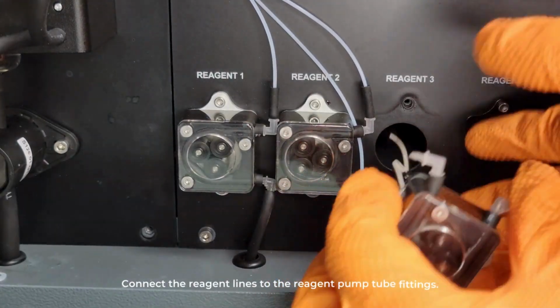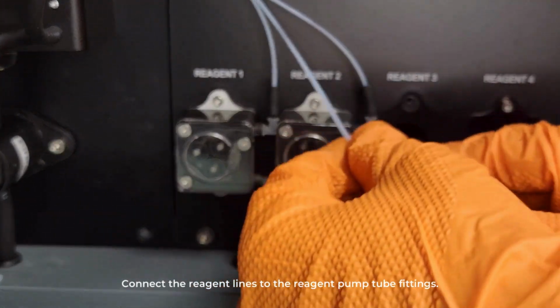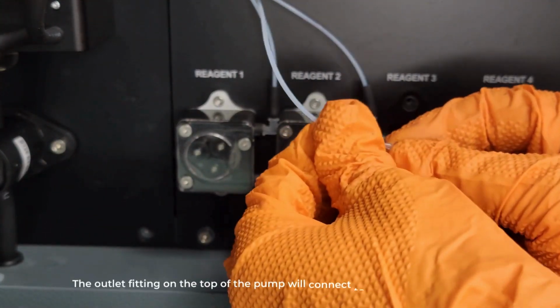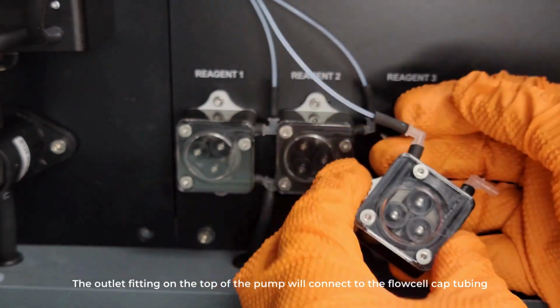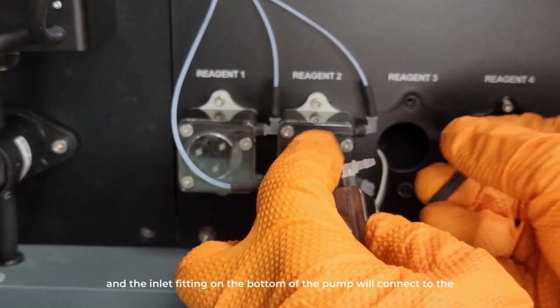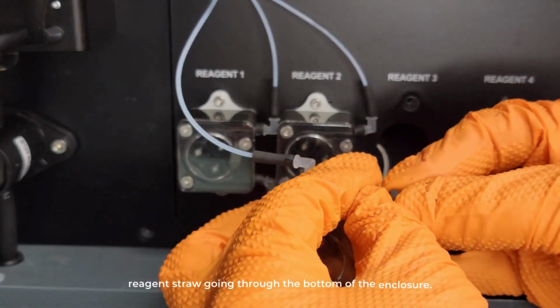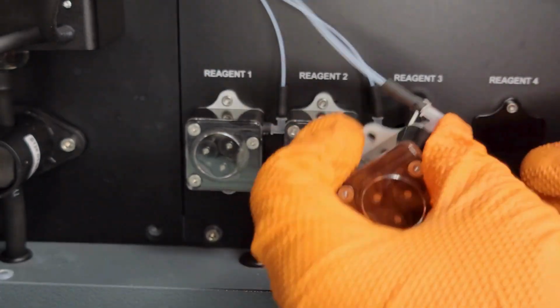Connect the reagent lines to the reagent pump tube fittings. The outlet fitting on the top of the pump will connect to the flow cell cap tubing, and the inlet fitting on the bottom of the pump will connect to the reagent straw going through the bottom of the enclosure.